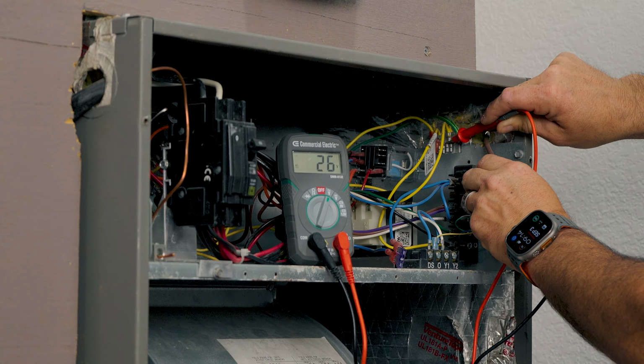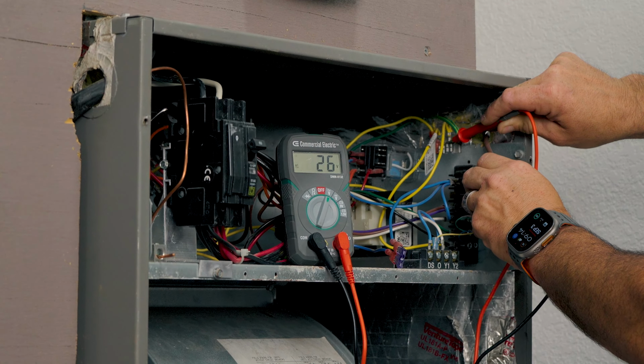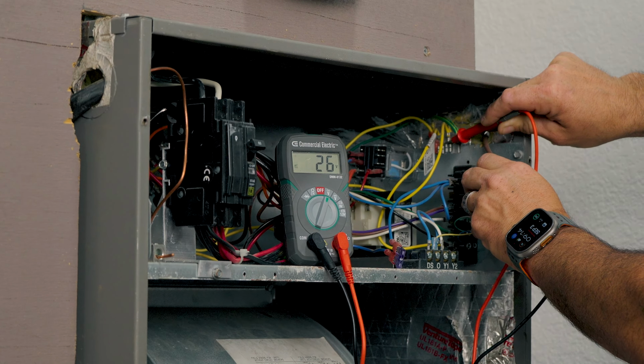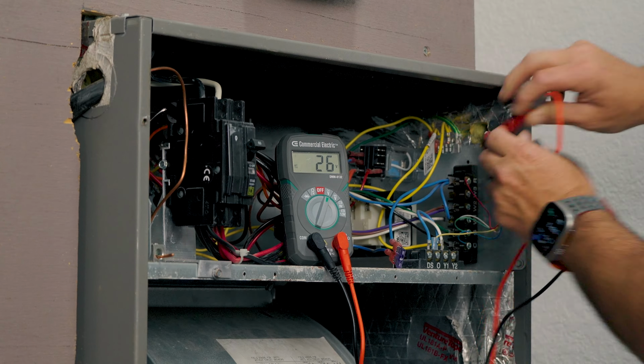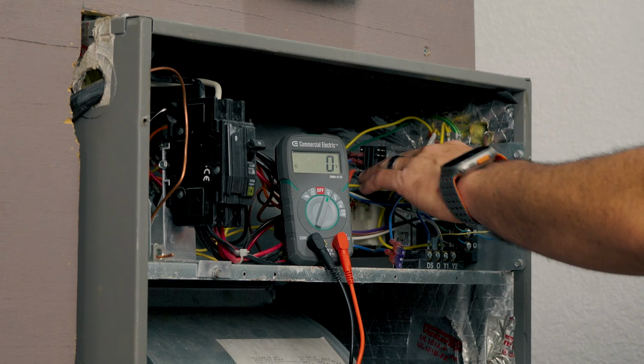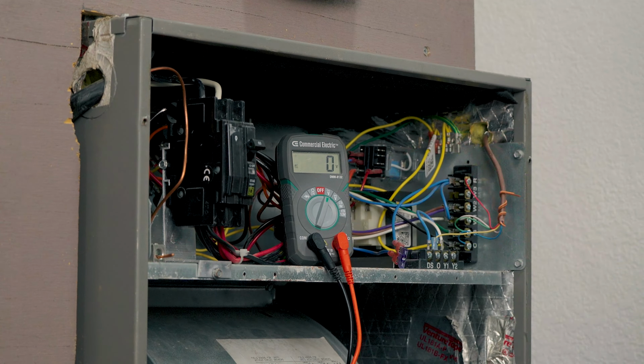You see on our tester we're getting 26 volts. This is correct. Anything between 21 to 27 is correct. If you are not getting voltage here, the next thing to do is replace this AC transformer. So we are getting voltage here, so we're going to move on.